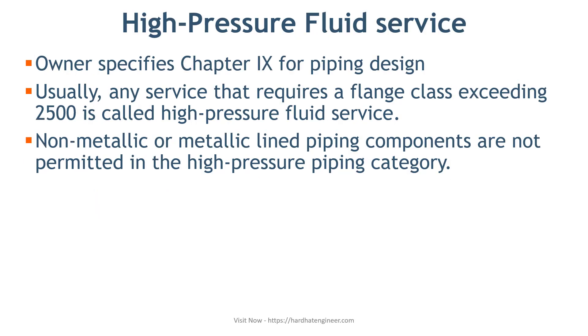The third fluid service is high-pressure fluid service. ASME B31.3 says that a fluid service for which the owner specifies chapter 9 for piping design and construction is called high-pressure fluid service. Usually, any service that requires a flange class exceeding 2500 is called high-pressure fluid service.